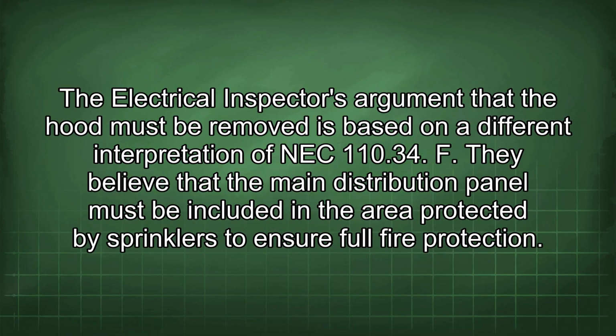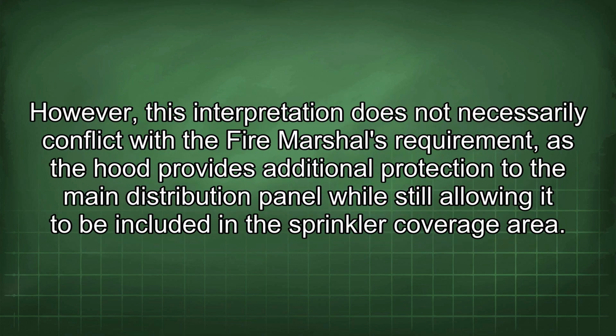The electrical inspector's argument that the hood must be removed is based on a different interpretation of NEC 110.34.F. They believe that the main distribution panel must be included in the area protected by sprinklers to ensure full fire protection. However, this interpretation does not necessarily conflict with the fire marshal's requirement, as the hood provides additional protection to the main distribution panel while still allowing it to be included in the sprinkler coverage area.